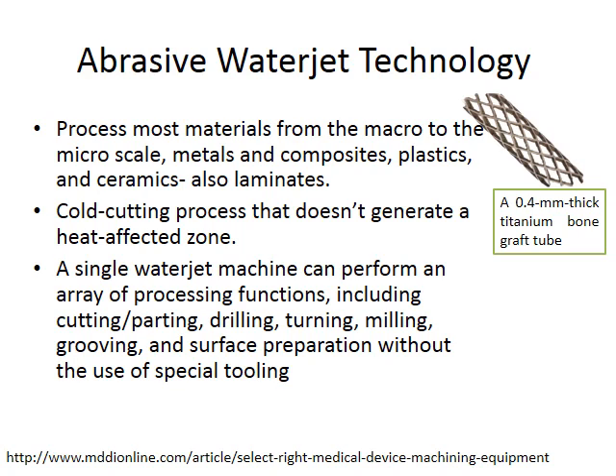Moving on to abrasive water jet technology. This can process most materials from the macro to the micro scale — metals, composites, plastics, ceramics, and laminates — making it attractive in medical device manufacturing where laser cutting may not work as well with plastics. It's a cold cutting process, so it generates no heat affected zone at all. A single water jet machine can perform an array of processing functions including cutting, drilling, turning, milling, grooving, and surface preparation without the use of special tooling.